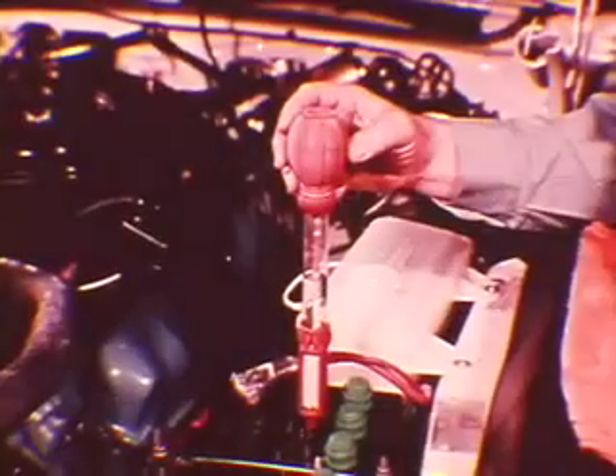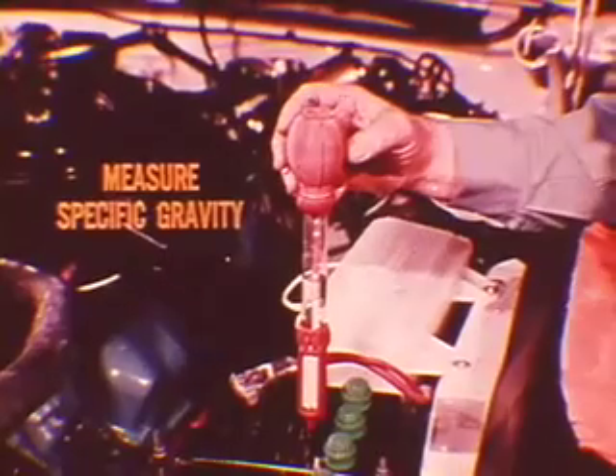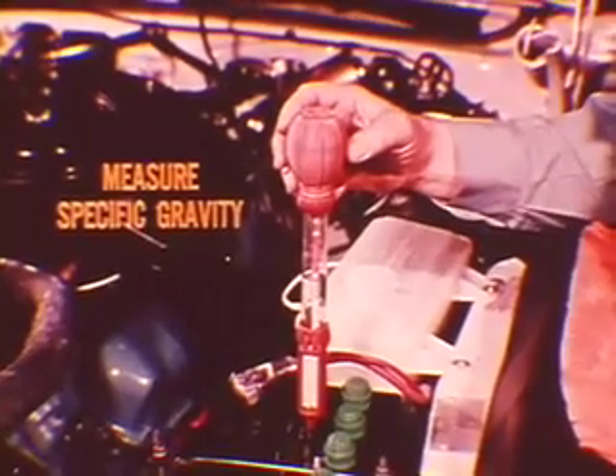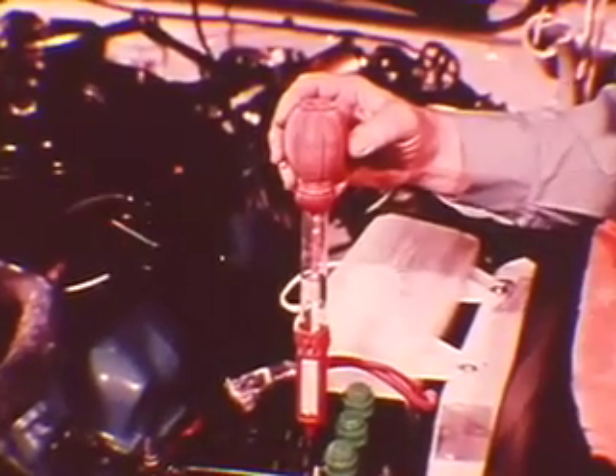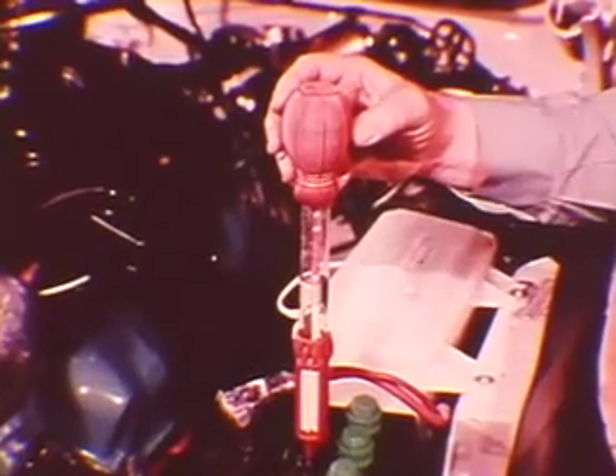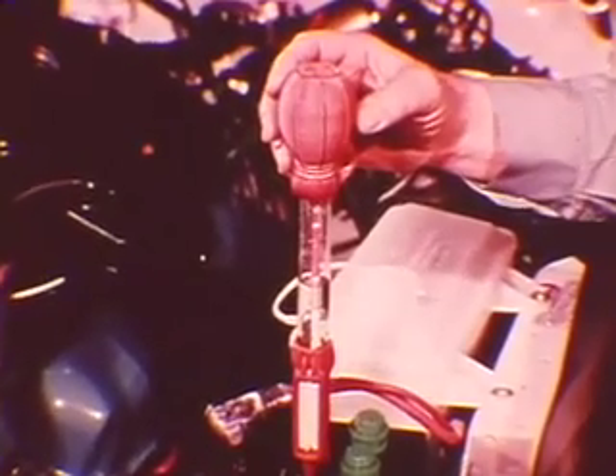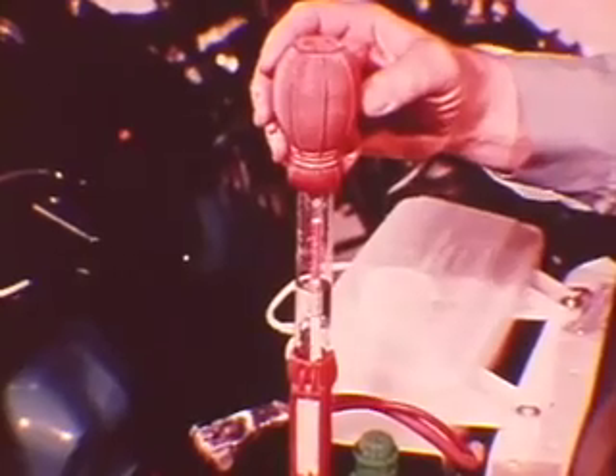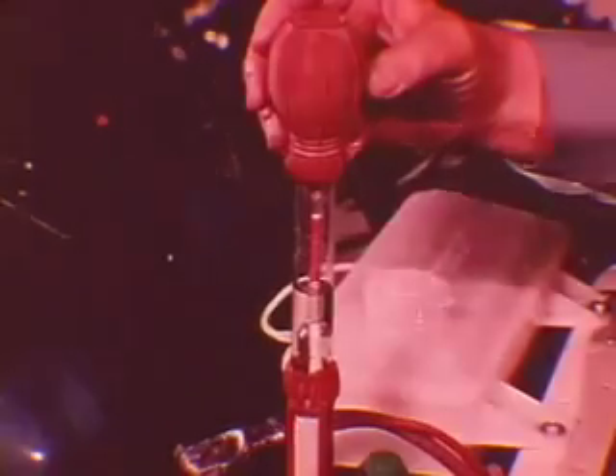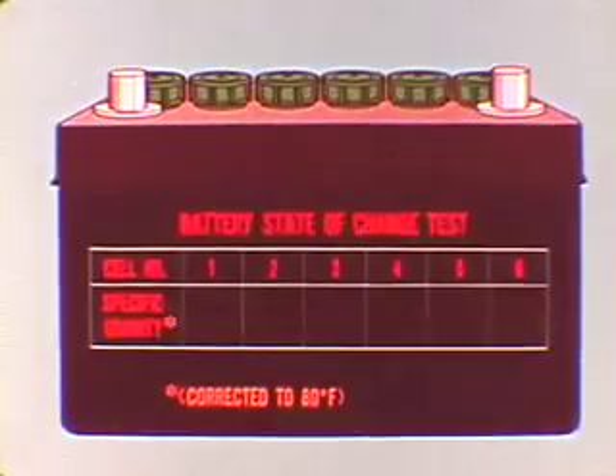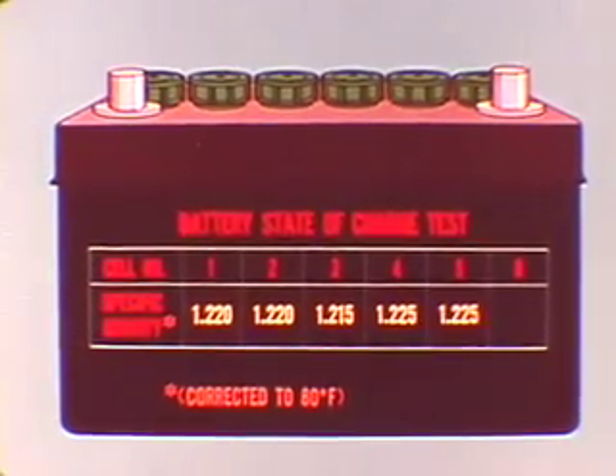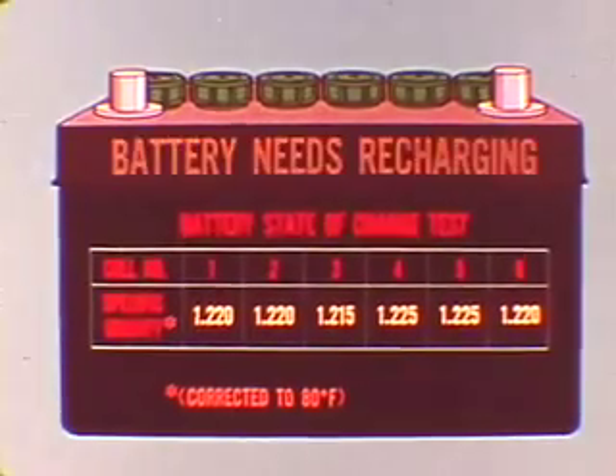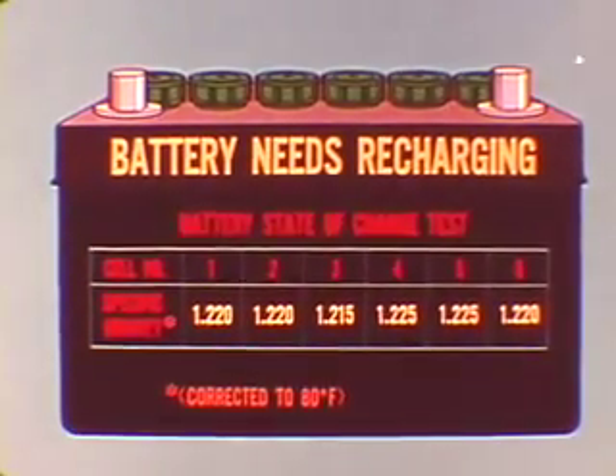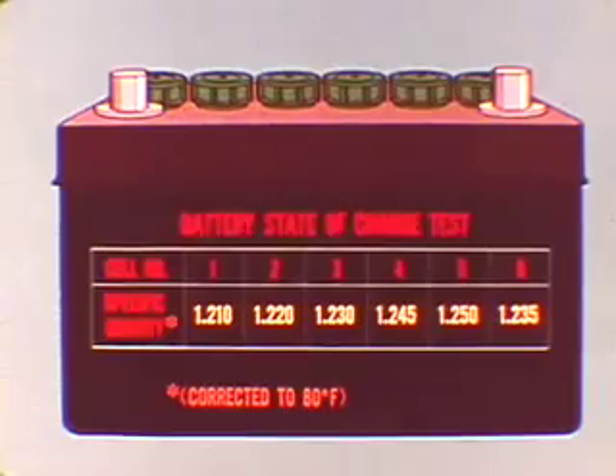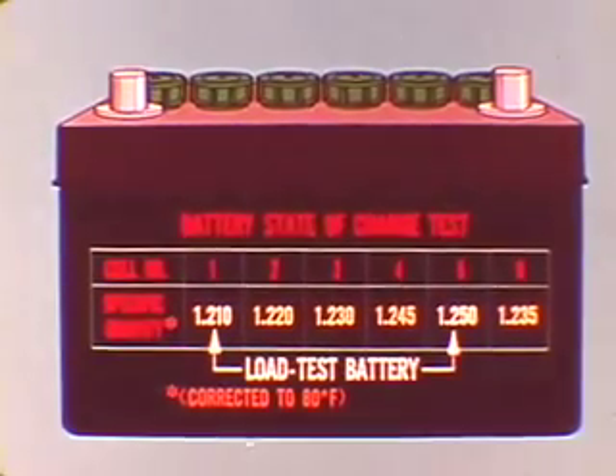The first step is to check the state of charge by measuring the specific gravity or concentration of the electrolyte. The principle is simple. The more acid there is in the electrolyte, the higher the state of charge, and the higher the hydrometer float will rise in the test sample. The most important part of your hydrometer test is noting any differences between cell readings. If all cell readings are uniformly low, the battery simply needs to be recharged. A sizable difference between cell readings means you should load test the battery.